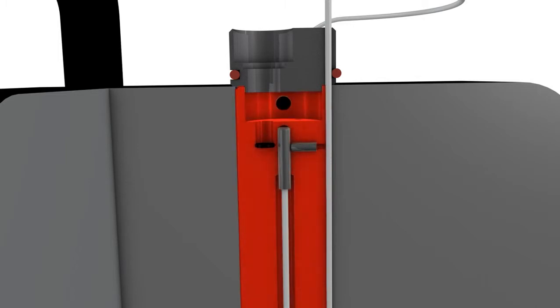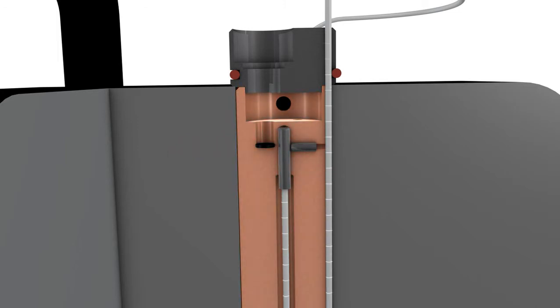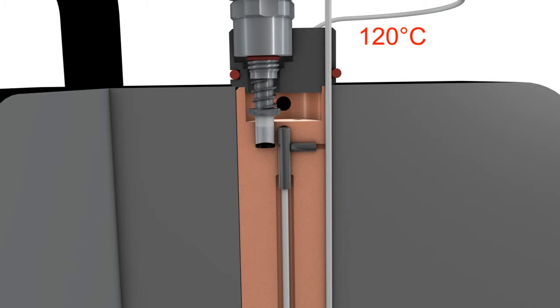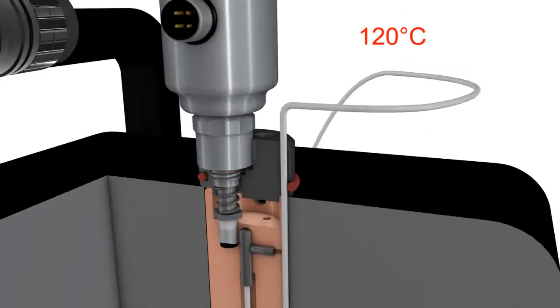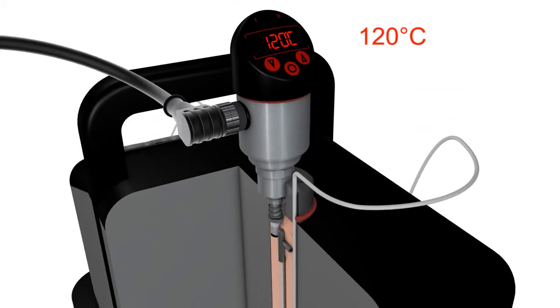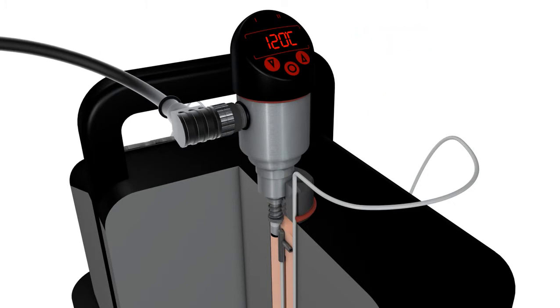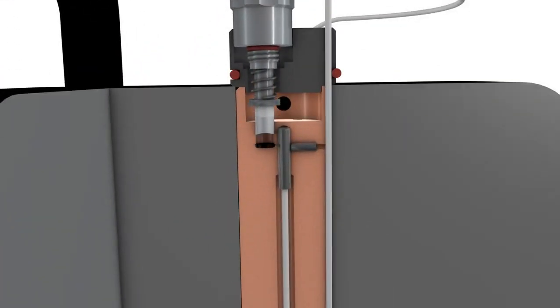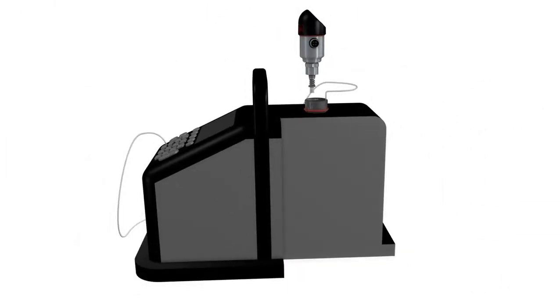We recommend that a reference sensor be mounted in the calibrator close to the clamp-on temperature sensor being calibrated. As you can see here, the reference sensor indicates 120 degrees Celsius. The sensor being calibrated is placed in the customized insert. After an adaptation period, the accuracy of the clamp-on temperature sensor can be assessed by comparing it with the reference sensor. It is then adjusted if necessary. Finally, the device is easily remounted on the pipe. The original process connection is unchanged.